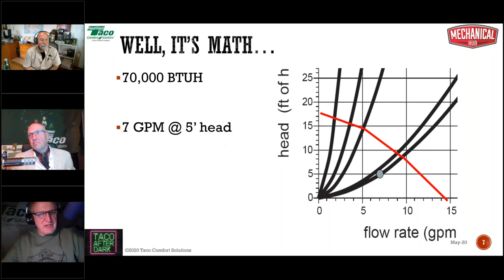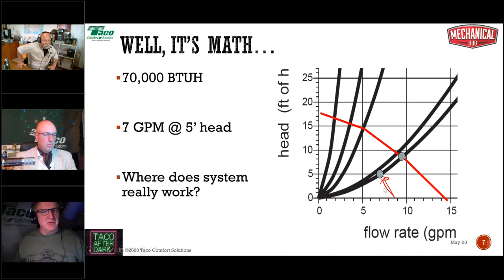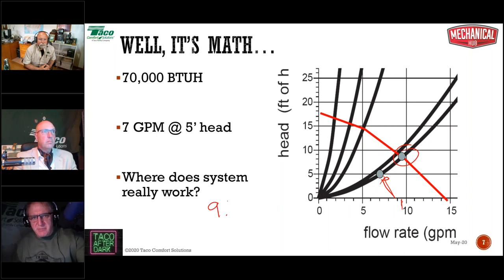In addition, we'll also calculate the head loss, which we've shown you already in previous segments. And we find the worst case head loss zone in our zone valve system is 5 feet of head. So when I size my circulator, it is going to have to deliver 7 gallons a minute at 5 feet of head. That's right here. Now, where does the system really work? Well, the system's really going to work where the system curve and the pump curve intersect, and that's way the heck out here. And that looks to be at about 9.5 GPM at, let's say, 8 feet of head.